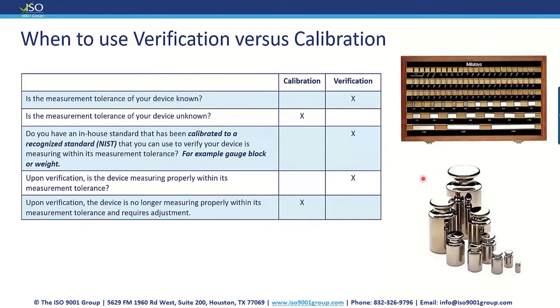Okay. Now, here's something else to think about. On verification, is the device measuring properly within its measurement tolerance? We put these weights on the scale, or we use these blocks to measure with our caliper, and it's measuring correctly within the tolerance. Why would I send that out for calibration?